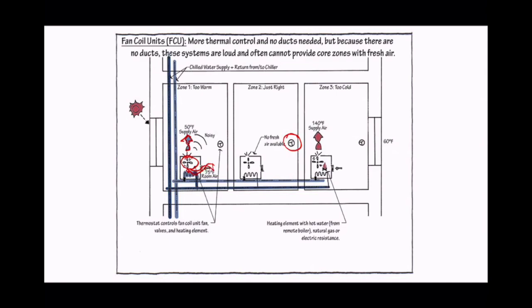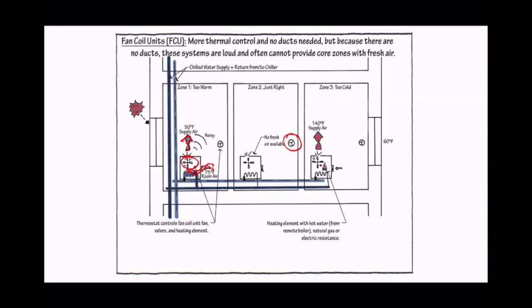The important differential between fan coil units on one hand and VRF and mini split on the other is that in those cases, we have refrigerant moving through the pipe. That is a huge difference. The actual phase change, the actual magic of air conditioning, is happening in the room in the case of VRF and mini split units. In the case of fan coil units, the refrigeration is happening somewhere else - in the basement, in the central plant, or somewhere else on the floor in the mechanical closet. Then chilled water is pumped in, and air is blown over the chilled water, and that's what's giving you the cooling.